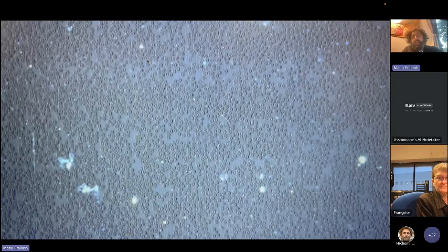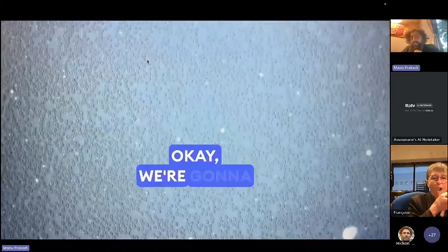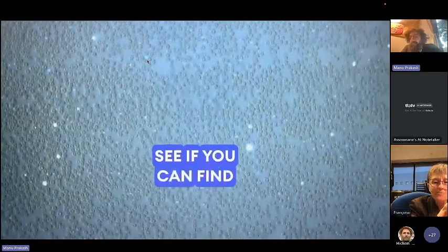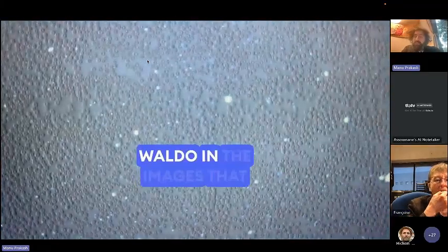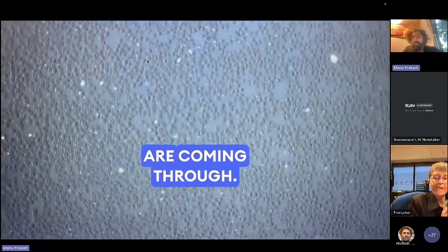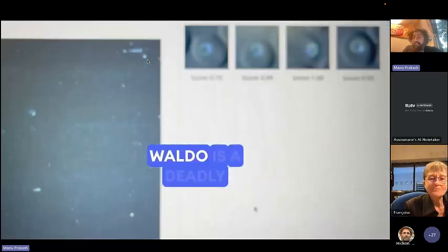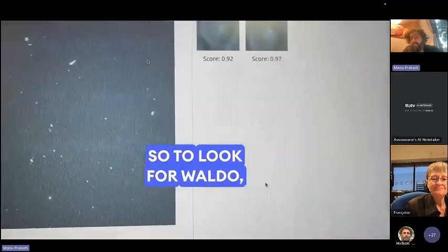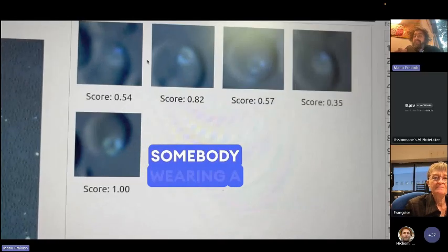So I'm about to show you a video, and what you will see is completely hands-free, autonomous diagnostics of malaria. These are malaria slides. This is a cell phone video, but it's kind of fun. And as I play this video, you'll watch that every single second the screen is changing. That's roughly between 10 to 15,000 blood cells that the instrument is analyzing in real time. And in real time, it's running a machine learning model to actually do the inference to say which cell is a parasite or not.